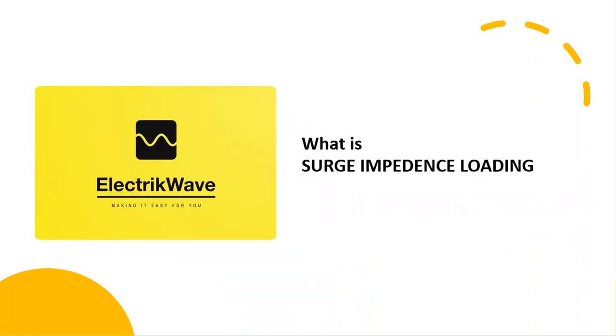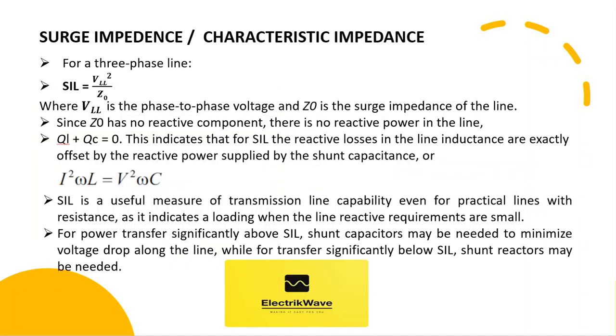Let's start with a discussion about what is surge impedance loading. For a three-phase line, surge impedance loading equals the square of the line-to-line voltage divided by Z0, where Z0 is the surge impedance of the line. Since Z0 has no reactive component, there is no reactive power in the line. QL plus QC equals 0.